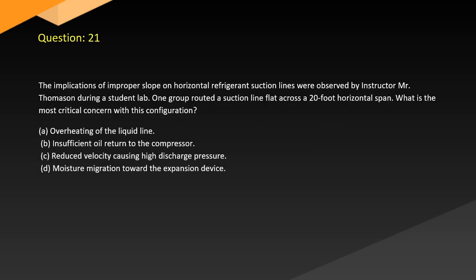Question 21. The implications of improper slope on horizontal refrigerant suction lines were observed by instructor Mr. Thomason during a student lab. One group routed a suction line flat across a 20-foot horizontal span. What is the most critical concern with this configuration? A. Overheating of the liquid line. B. Insufficient oil return to the compressor. C. Reduced velocity causing high discharge pressure. D. Moisture migration toward the expansion device.